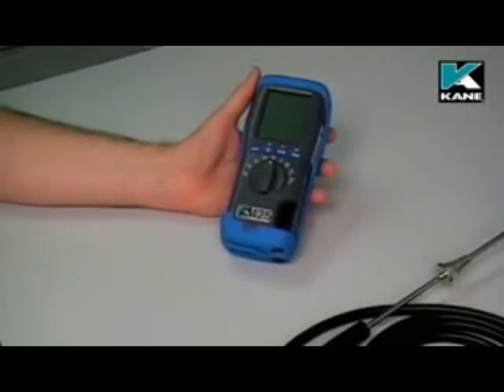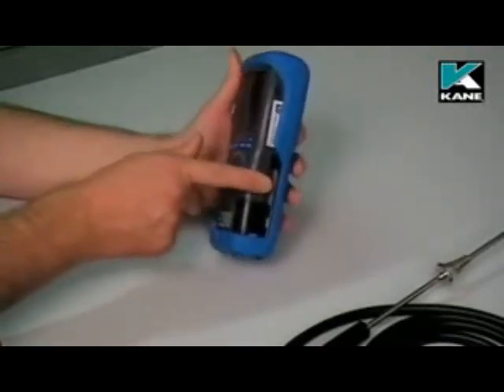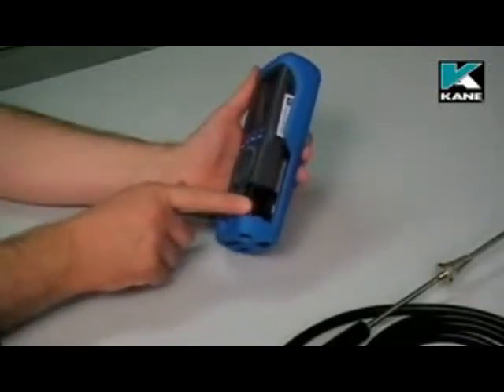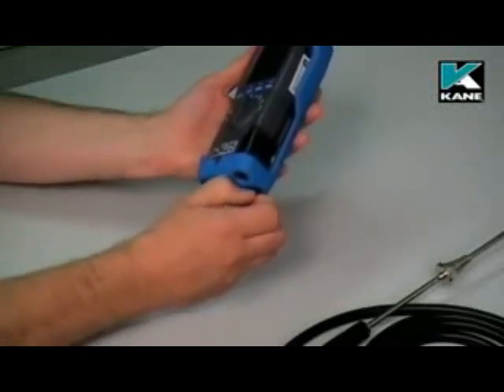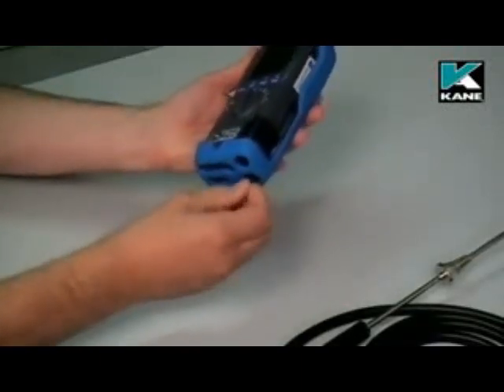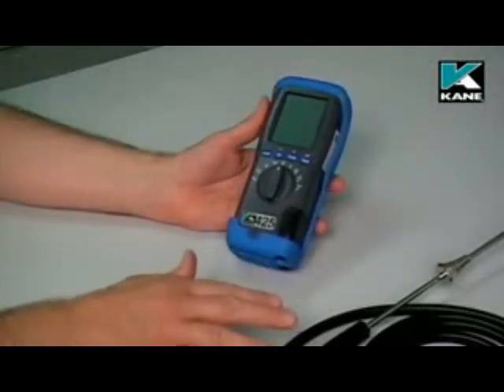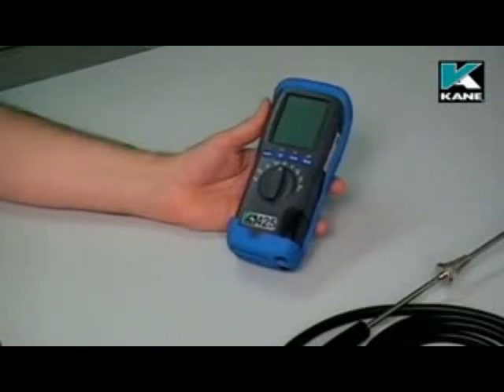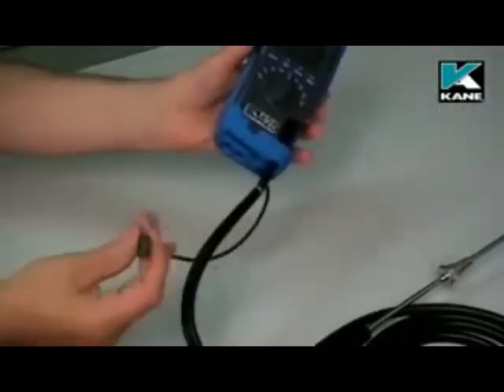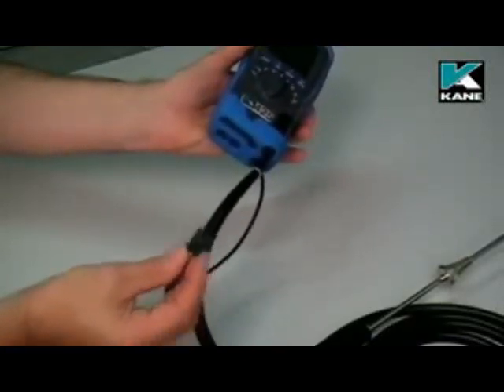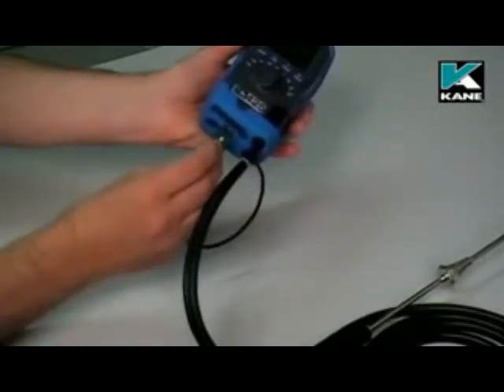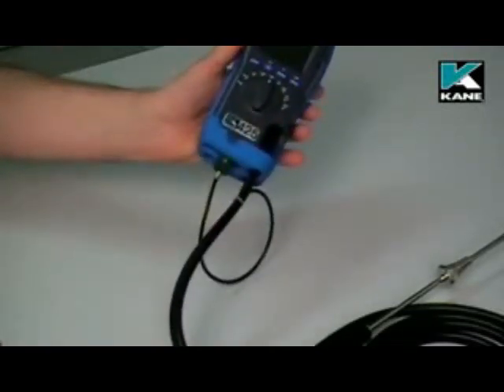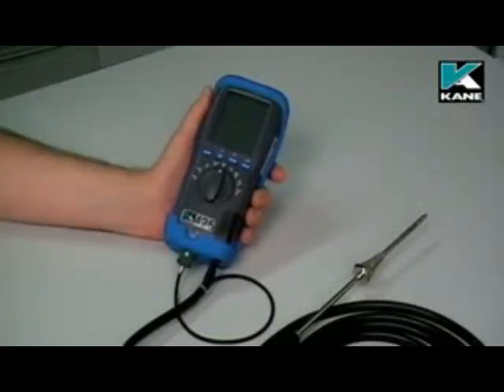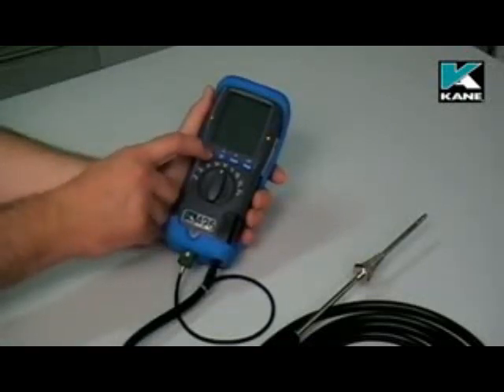Before using the analyzer, firstly check that the particle filter is clean. Also check that the water trap has no moisture in it. If necessary, gently remove the rubber bung and then replace it. Make sure that there's no water left in the flue probe hose from your previous tests. Connect the hose to the bottom of the water trap. Connect the plug of the thermocouple into T1. Normally if you have the head of the screw pointing towards you, that makes sure that the connections are around the right way. When you want to use the analyzer, the first thing to do is position the flue probe in fresh air, to make sure you're not in an area with any carbon monoxide. Then press the on button.